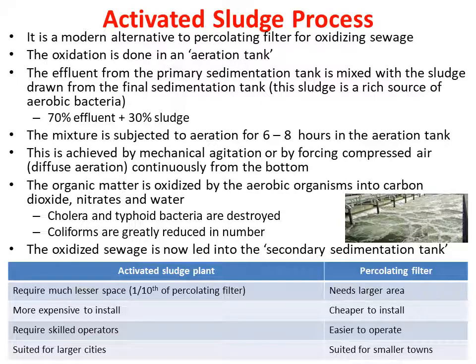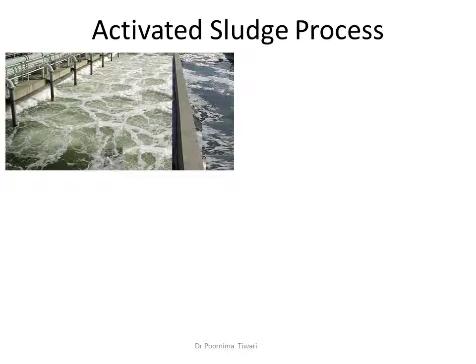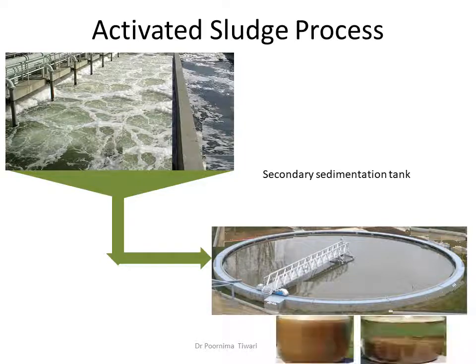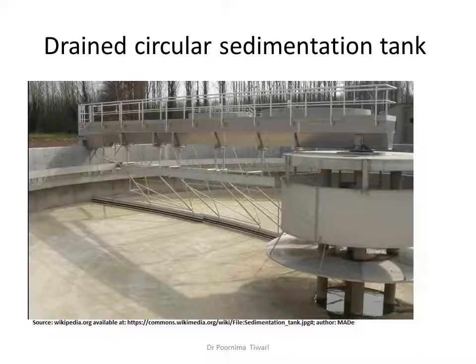Comparing the activated sludge plant with the percolating filter plant: the activated sludge plant requires only one-tenth of the space compared to the percolating filter, but it is more expensive to install and requires more skilled operation. Hence, the activated sludge plant is more suited for larger cities. Pictures show the sewage being agitated in the aeration tank — it appears to be boiling due to diffuse aeration. The fully oxidized sewage is then led into the secondary sedimentation tank where the activated sludge quickly settles, removed by slowly rotating scrapers at the bottom.